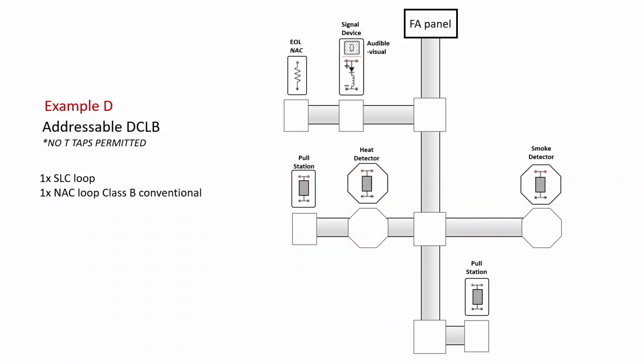So first thing I'm going to start with is my NAC loop. That's going to be, again, 14 gauge single conductor cables, or single conductors pulled into EMT. So exactly the same as our conventional system. Next is going to be with SLC cable. Now the main difference between this being an addressable versus the conventional is that addressable doesn't have any end-of-line resistors.